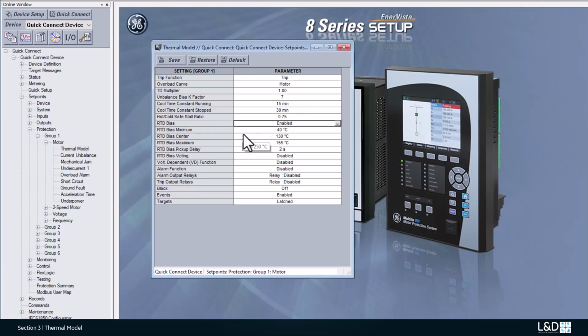The RTD bias will enable the temperature from the stator RTD sensors to be included in the calculation of the thermal capacity. This model determines the thermal capacity used based on the temperature of the stator and is a separate calculation from the overload thermal model for calculating the thermal capacity used.